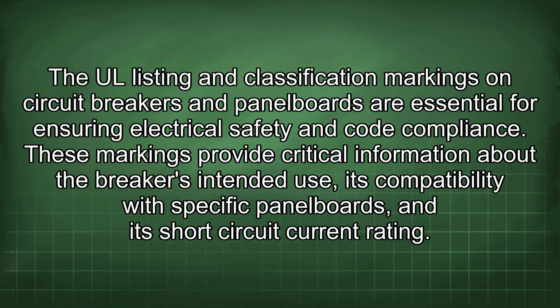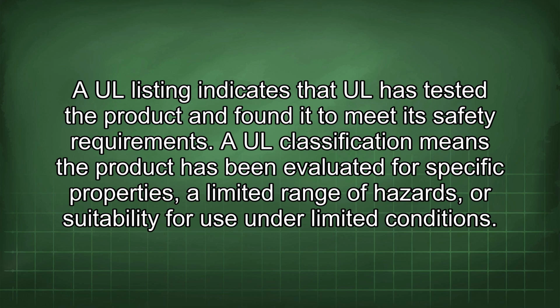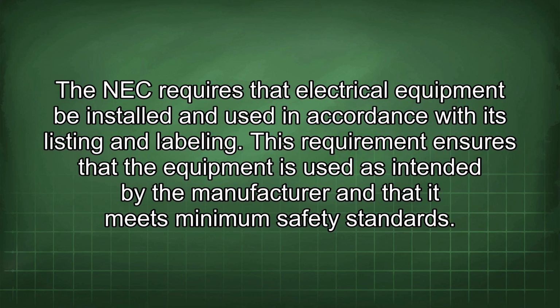The UL listing and classification markings on circuit breakers and panel boards are essential for ensuring electrical safety and code compliance. These markings provide critical information about the breaker's intended use, its compatibility with specific panel boards, and its short circuit current rating. A UL listing indicates that UL has tested the product and found it to meet its safety requirements. A UL classification means the product has been evaluated for specific properties, a limited range of hazards, or suitability for use under limited conditions. The NEC requires that electrical equipment be installed and used in accordance with its listing and labeling. This requirement ensures that the equipment is used as intended by the manufacturer and that it meets minimum safety standards.